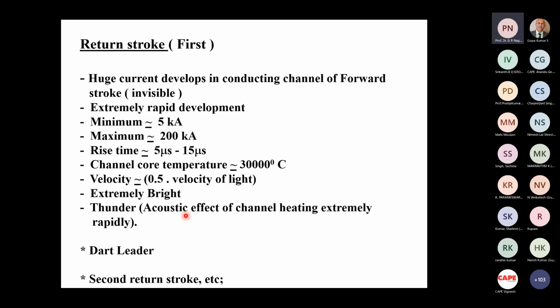Then we have seen that the return stroke has got huge currents. We have seen the reason for that. The huge current develops in the conducting channel of the forward stroke. The forward stroke itself is invisible. The return stroke develops extremely rapidly. The minimum current in the return stroke is about 5 kiloamperes. It can go up to 200 kiloamperes. And then the rise time, the time in which the current reaches the peak, is typically 5 microseconds to 15 microseconds. In some rare cases, it can happen as rapidly as 2 microseconds. It can sometimes take 30 to 60 microseconds or even more. So rise time typically is 5 microseconds to 15 microseconds.